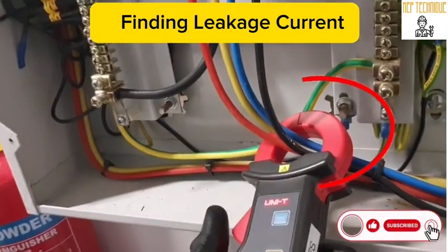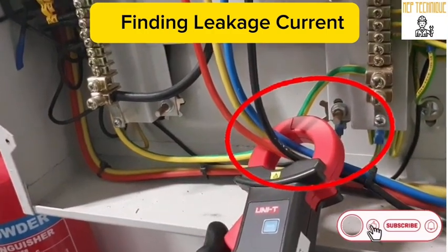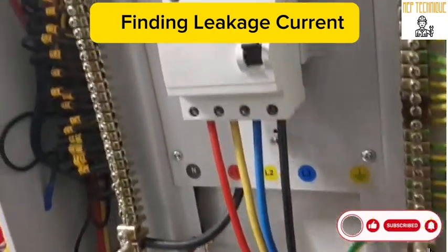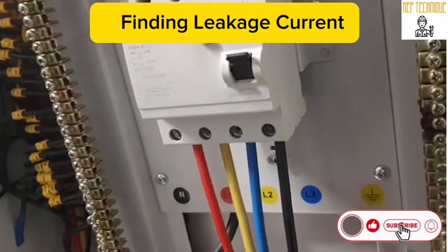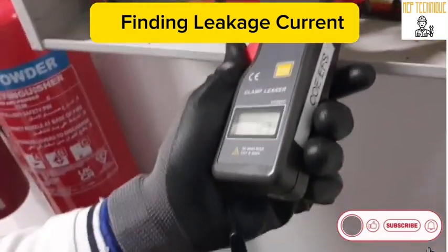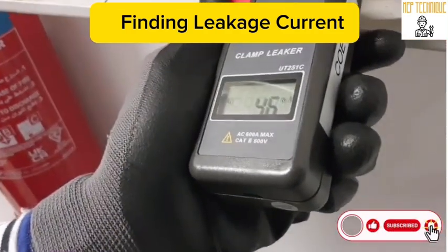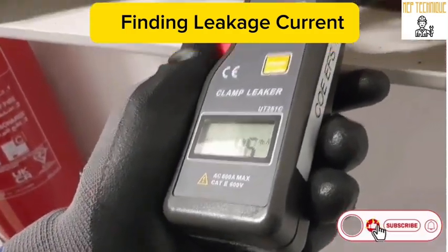When you measure the leakage current, please clamp together both phase and neutral. For single phase, clamp one phase and neutral together, and for three phase, clamp all phases and neutral together. Don't check them separately.